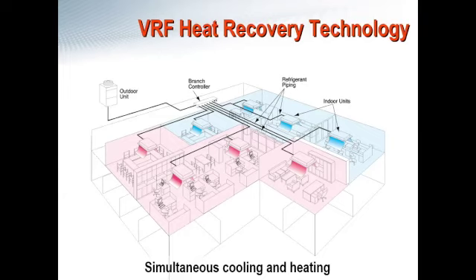When you're designing for a heat recovery system or an R2 system, if you're looking at a Mitsubishi product, we really try and balance the load diversity exactly, or as exact as possible. So one thing to consider is if you're going with a heat pump, you might want to service an entire facade of a building or an entire building in and of itself. Anywhere that you might think a load profile is going to be very similar.